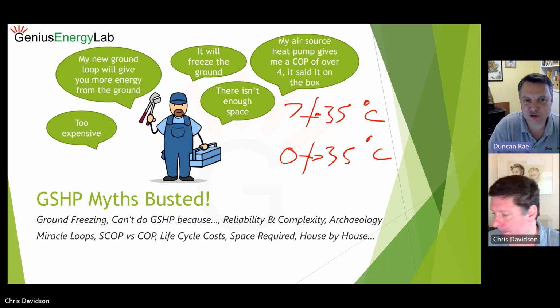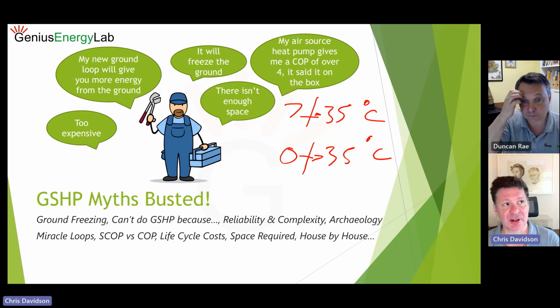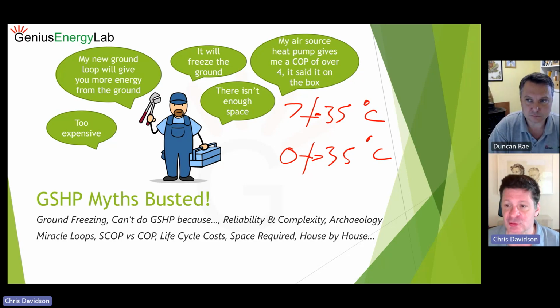Are there not other initial costs, though, that start to become a factor when you look at an entire project holistically, such as the electrical infrastructure? Absolutely. So because air source heat pumps are going to be consuming more electricity, they need bigger electrical infrastructure to support them. There's a cost associated with putting that electrical infrastructure in. Other points to make on air source also is that they require roof space or high level space to operate. So for example, there's a project in London we're looking at the moment where we took air source heat pumps out of level 10, which is the prime retail space in that building, and we moved that into the basement, and we got about £4 million extra annual revenue for that space that was then able to be let out. So there are other economics that come into it other than just initial cost and run cost savings as well.